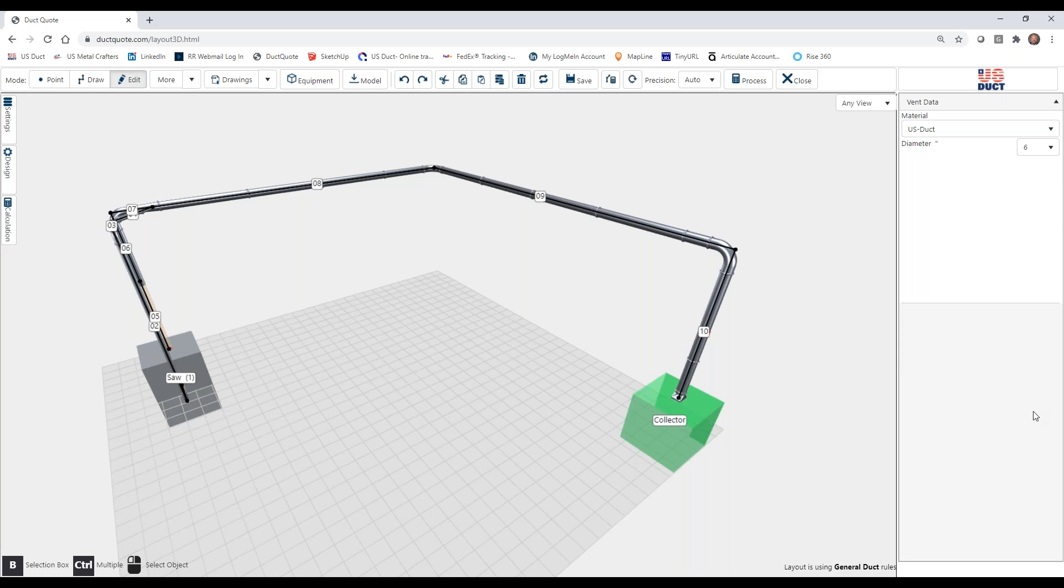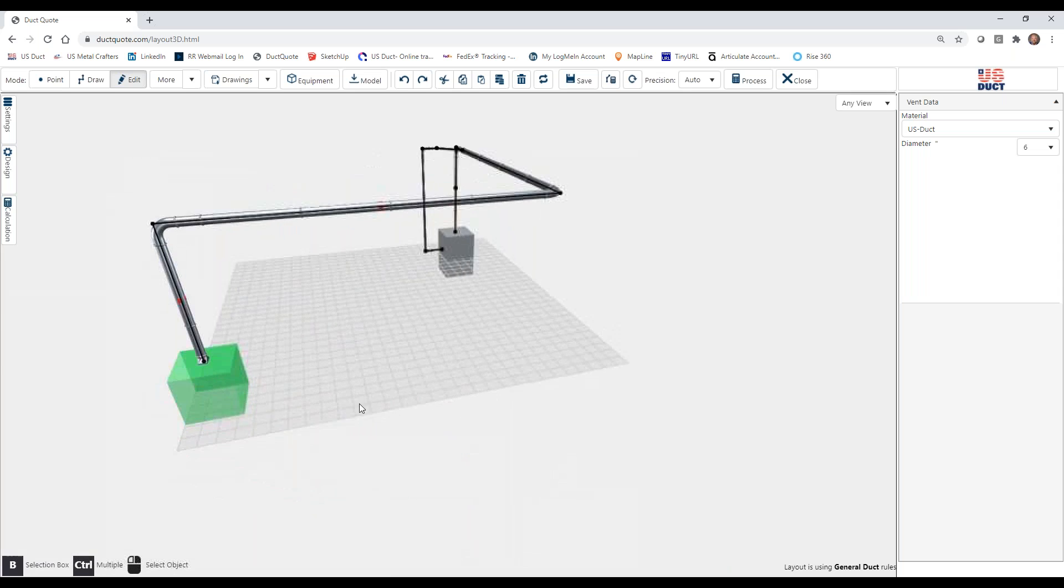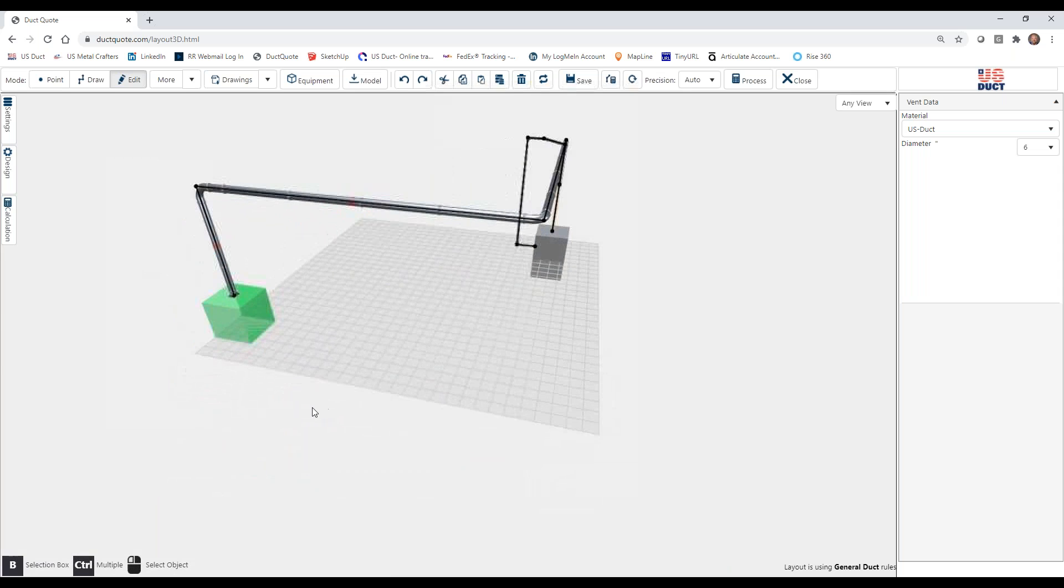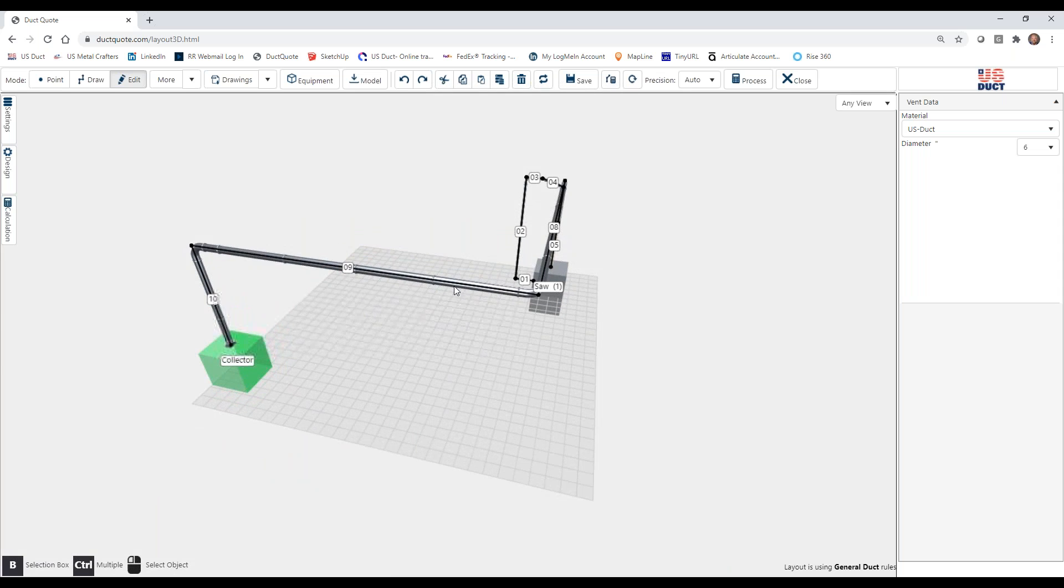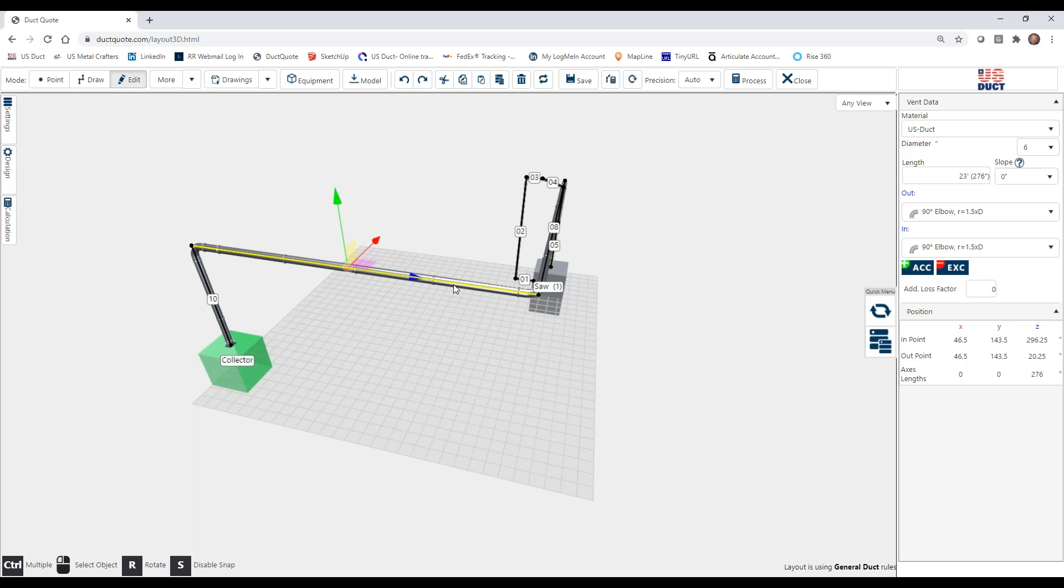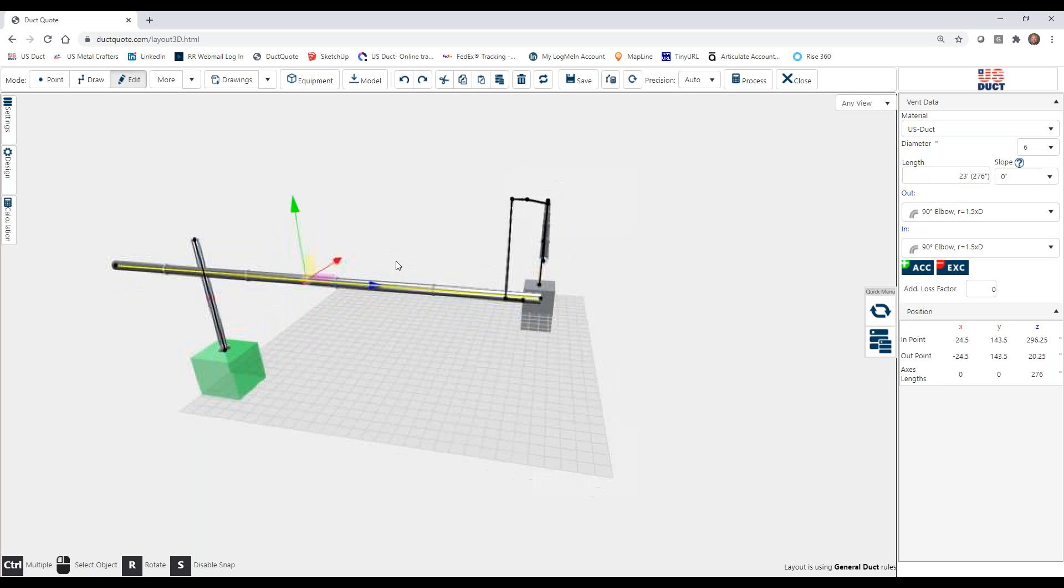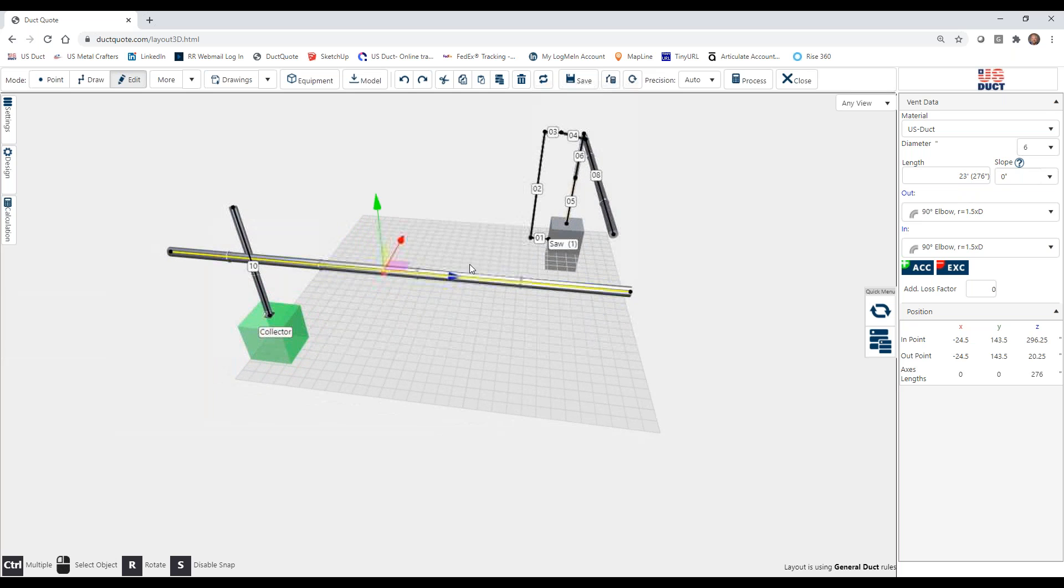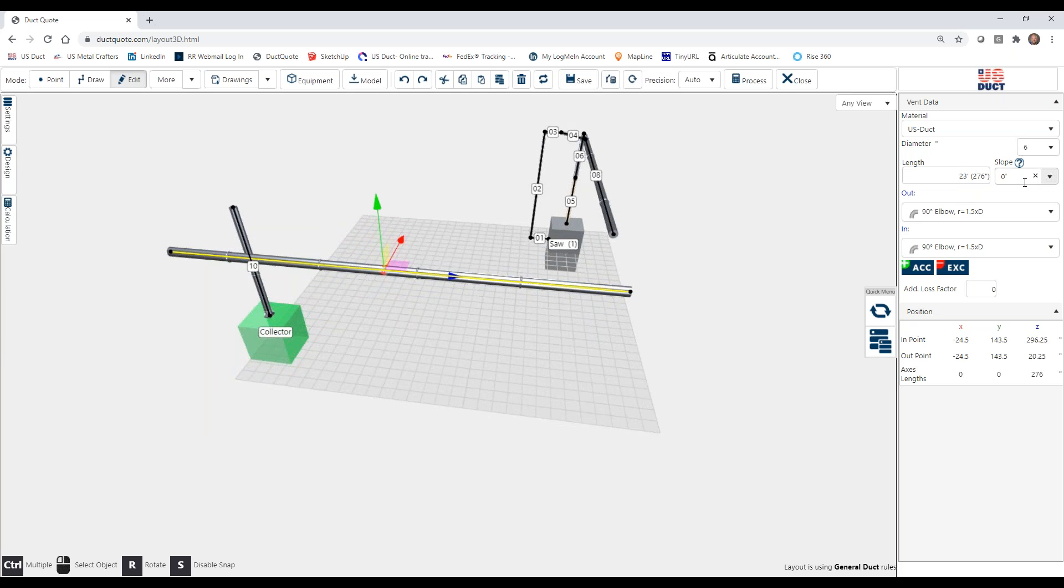Then we come to slope. Now this is very interesting. I'm going to actually disconnect a pipe. So we have a section of duct here. We look up slope. There's currently zero slope. In other words, it's parallel with the floor. I can actually select from a drop-down list, very common slope would be one quarter inch per foot.